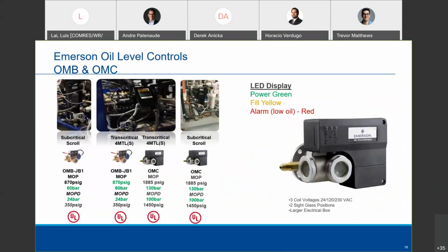From an oil level control, the OMC is a new device, and I mentioned 130 bars, a high pressure rating, and it even has a maximum operating pressure differential of 1,450 pounds. You may say, well, why would anybody want something so high? Well, if you're using a high pressure oil system, you can actually go from transcritical pressures all the way down to this device without dropping the pressure. That knocks a component out of the system, like an oil reservoir, which is at a lower pressure. So some users want that.